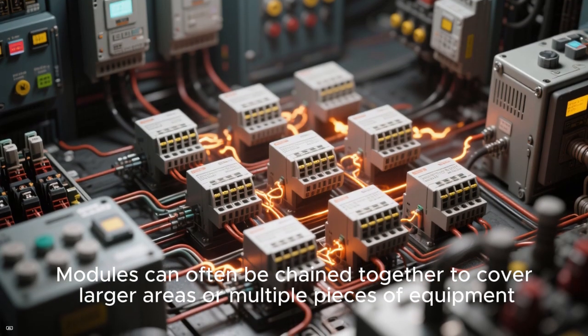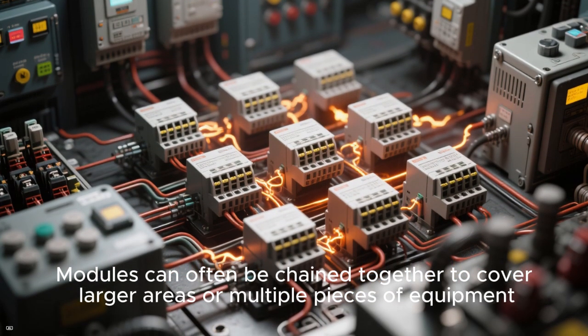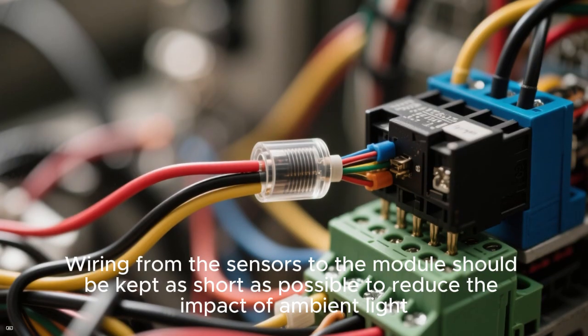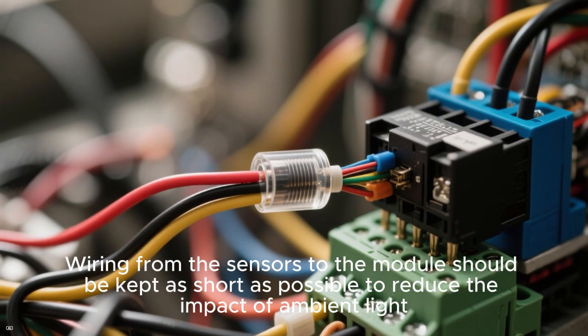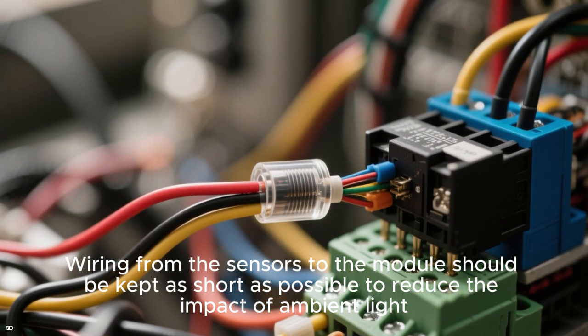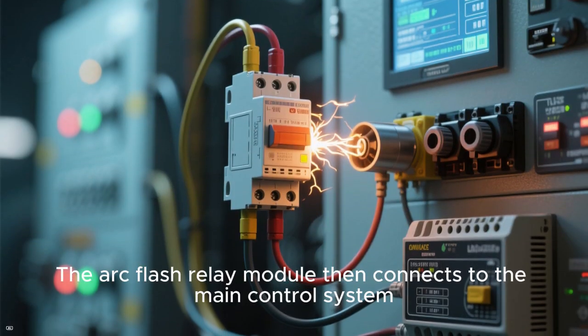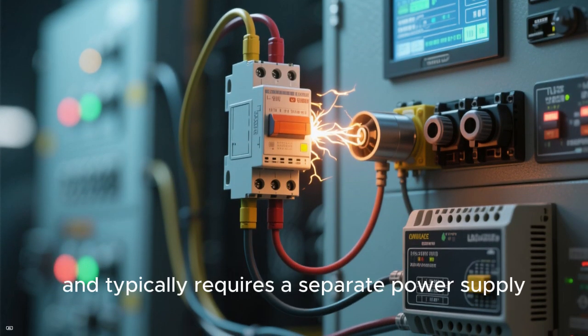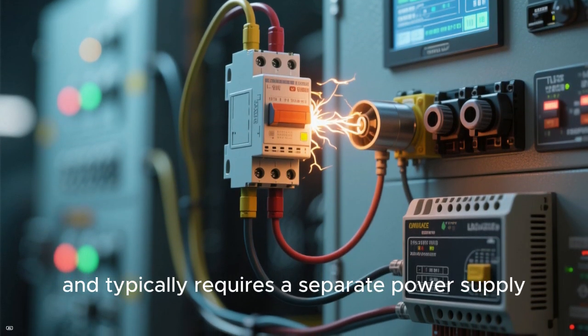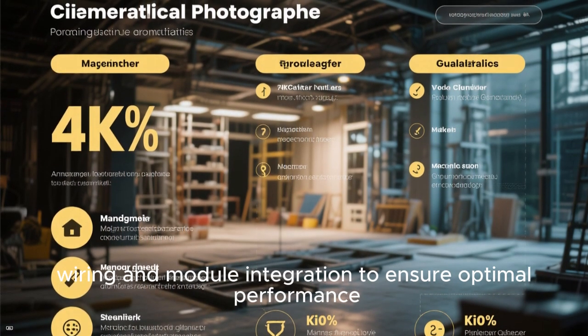Modules can often be chained together to cover larger areas or multiple pieces of equipment. Wiring from the sensors to the module should be kept as short as possible to reduce the impact of ambient light. The arc flash relay module then connects to the main control system and typically requires a separate power supply. It's important to follow manufacturer guidelines for sensor placement, wiring, and module integration to ensure optimal performance.